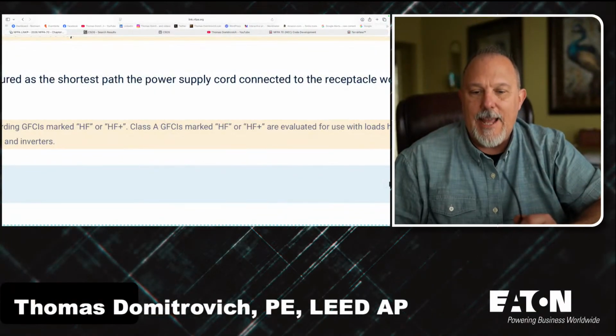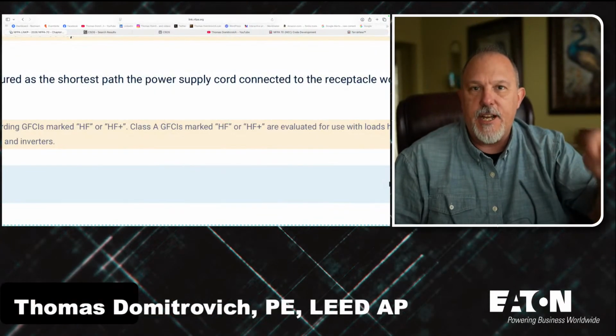The comment I get frequently is that's not a requirement, and because informational notes cannot have requirements, they are absolutely correct. But the key thing to recognize is what we say here: Class A GFCIs marked HF or HF plus. The key thing is it's a Class A GFCI.